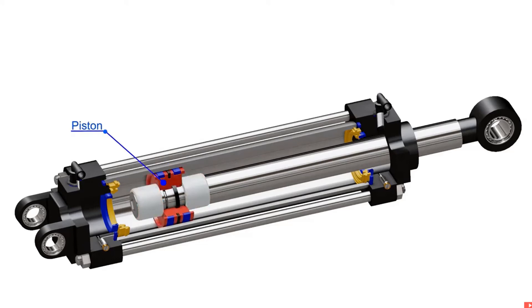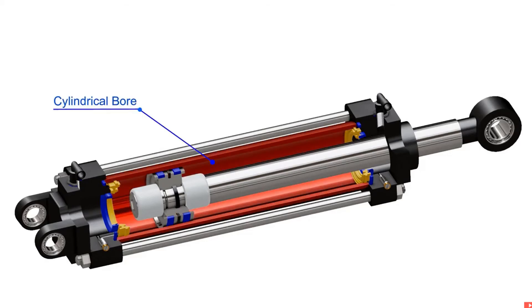The piston reciprocates back and forth when there is pressure difference between any of the two sides. A static seal ensures air tight sealing between the piston and rod. Piston guide rings are assembled to prevent metal to metal contact of piston and cylinder. Piston seal provides air tight sealing between the cylinder and piston. This whole assembly then goes into a cylindrical bore.